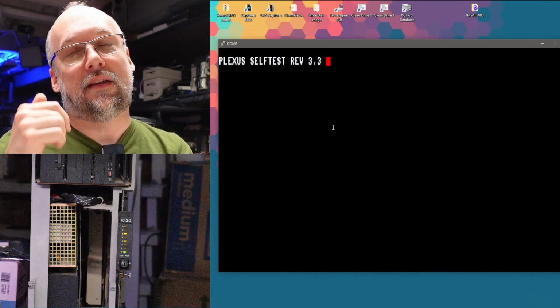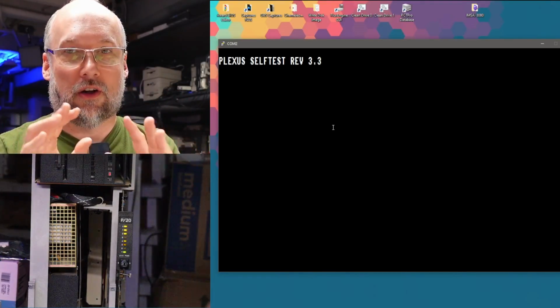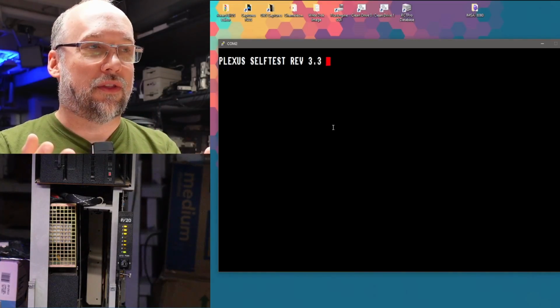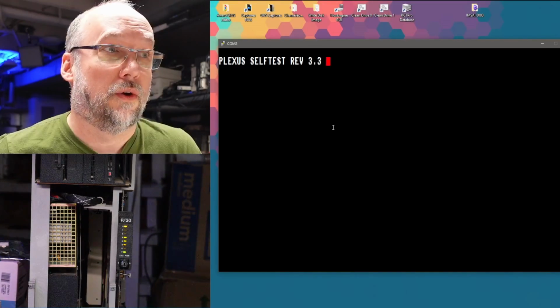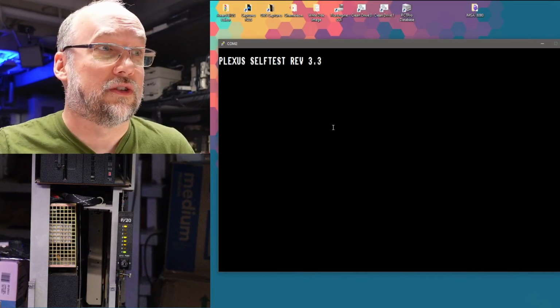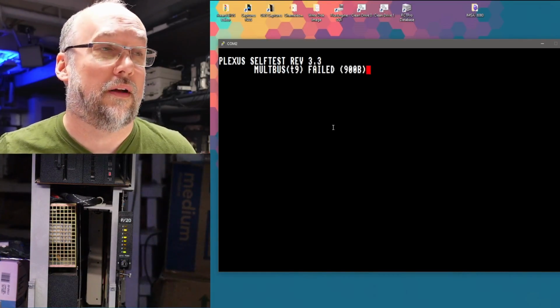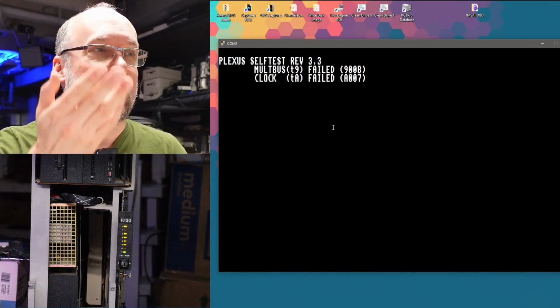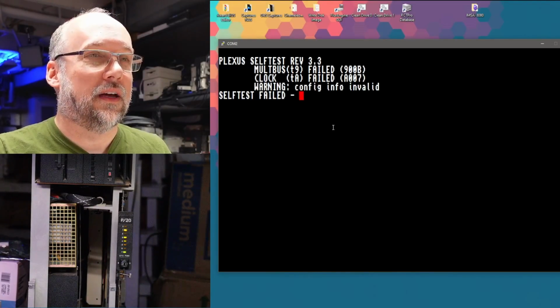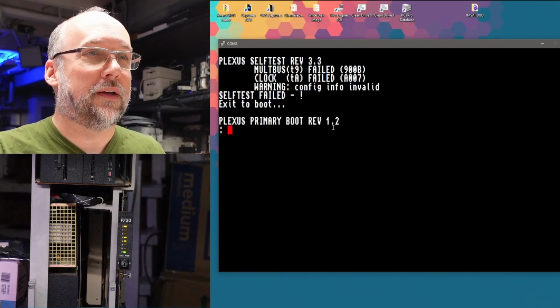So the fact that the multibus card cage is not installed on the front of the machine, I don't think is actually a problem. So we might be dealing with another fault. Maybe there's some select logic issues or whatever that's happening on here. And yeah, we're getting those errors again. All right, self-test failed. Hit exclamation point to bypass.